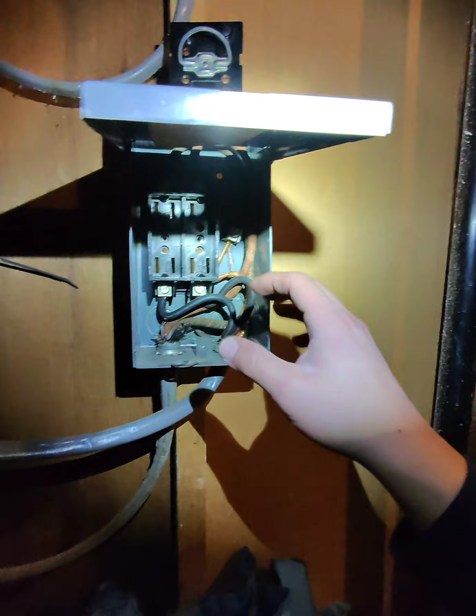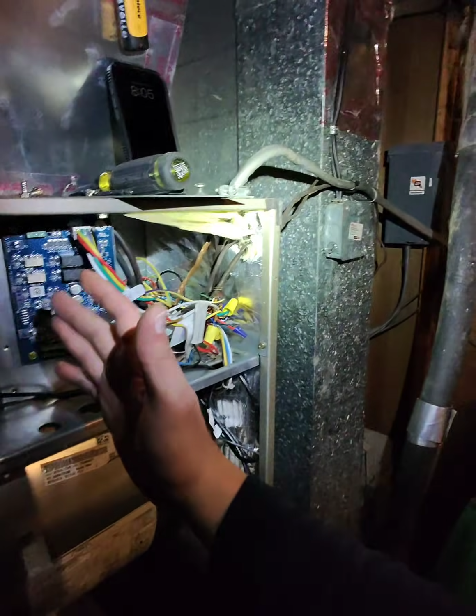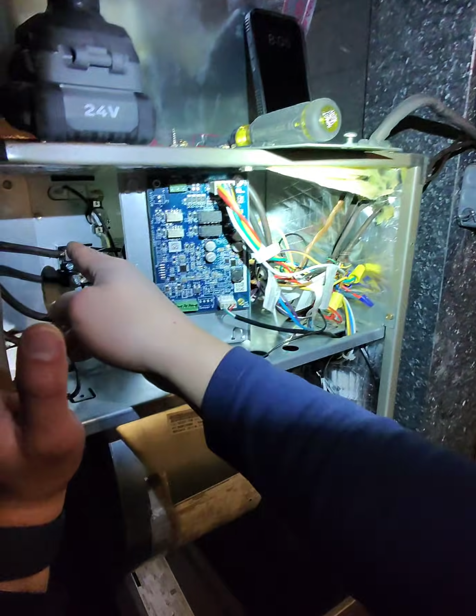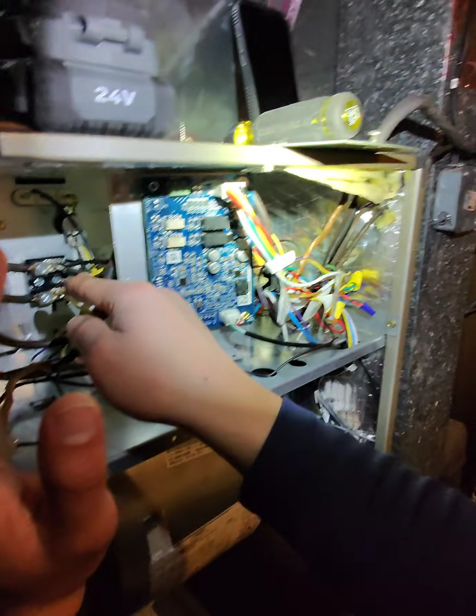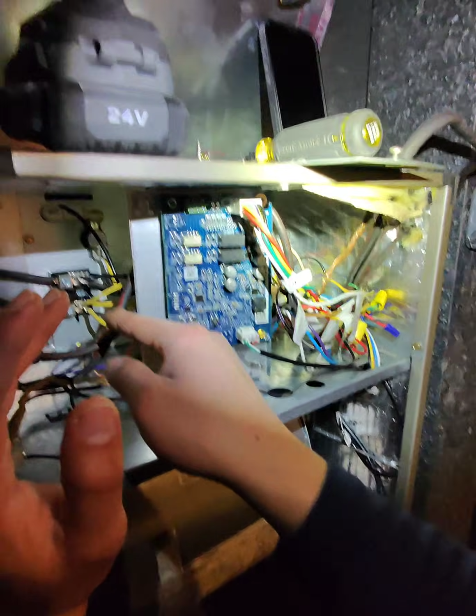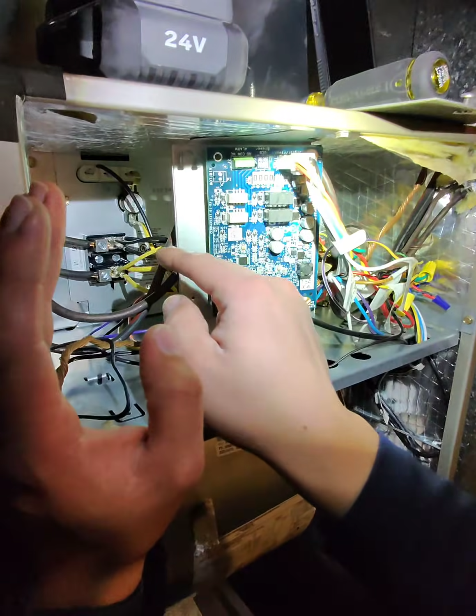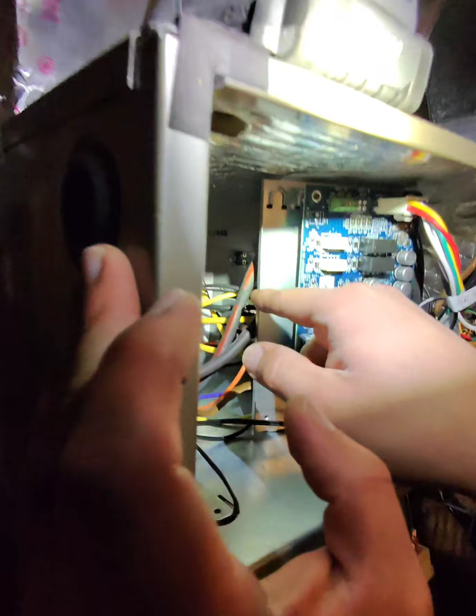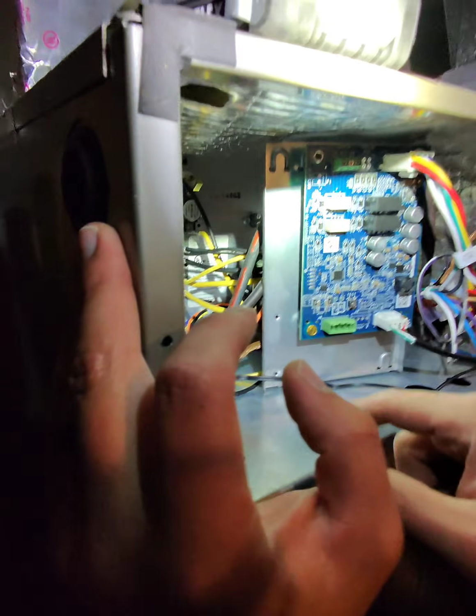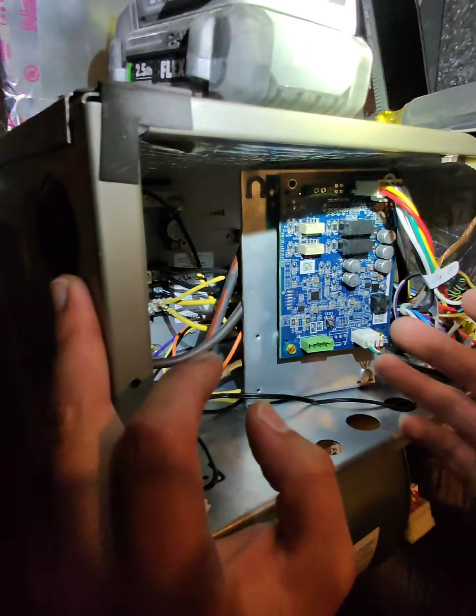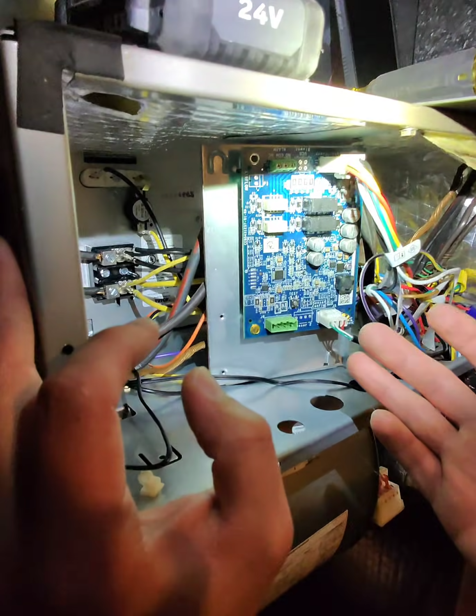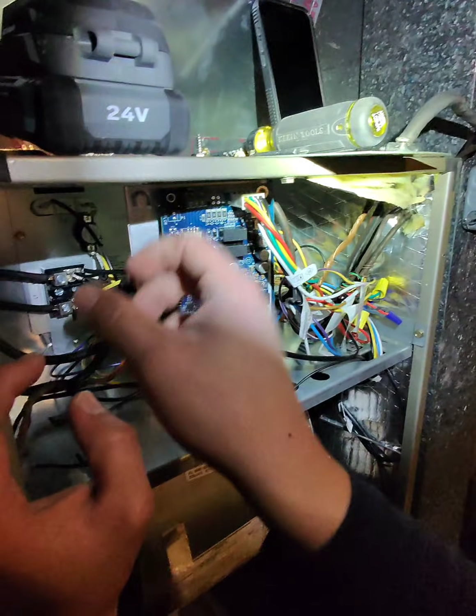So usually it's good to have fuses on here. Now if you have this non-fused situation, then it's good to have a circuit breaker built into the heater package. The heater package is this, that's your electric resistance heater. Since it has an N in there at the last three digits, N10, that signifies there's no fuse built into it. There's no fuses or circuit breaker.